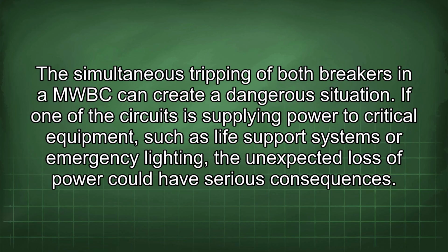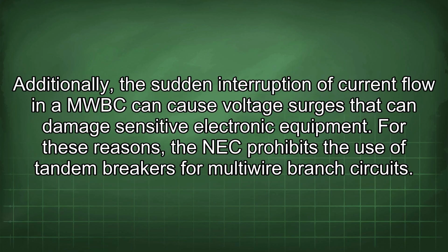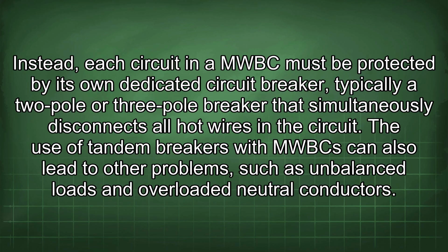The simultaneous tripping of both breakers in MWBC can create a dangerous situation. If one of the circuits is supplying power to critical equipment, such as life support systems or emergency lighting, the unexpected loss of power could have serious consequences. Additionally, the sudden interruption of current flow in the MWBC can cause voltage surges that can damage sensitive electronic equipment. For these reasons, the NEC prohibits the use of tandem breakers for multi-wire branch circuits. Instead, each circuit in the MWBC must be protected by its own dedicated circuit breaker, typically a 2-pole or 3-pole breaker that simultaneously disconnects all hot wires in the circuit.